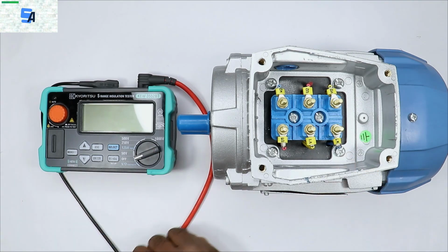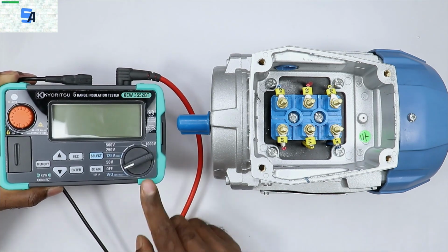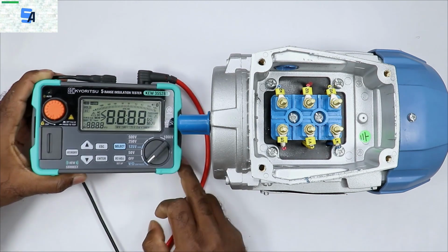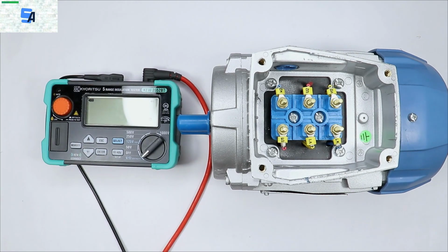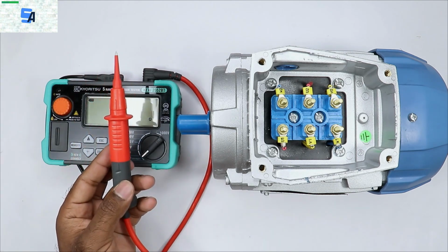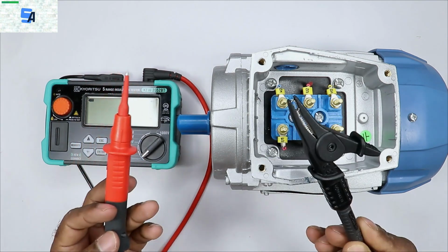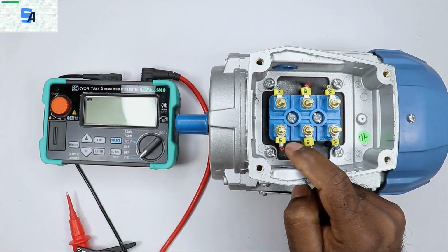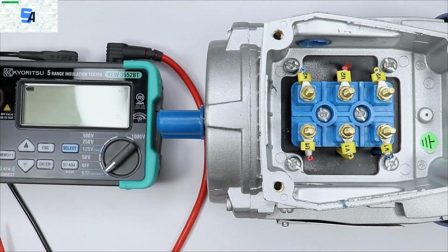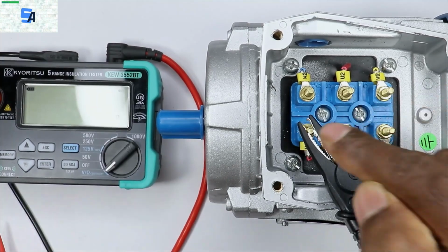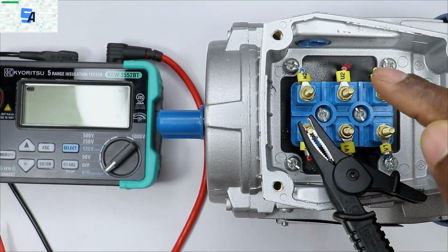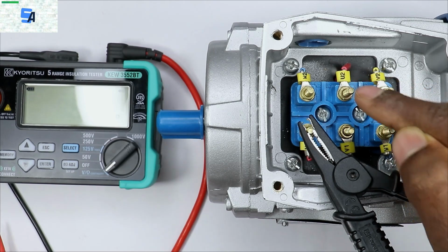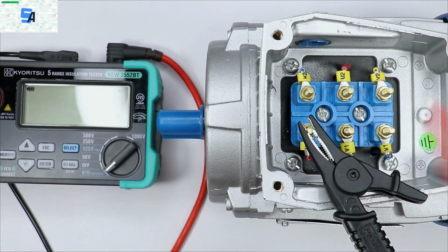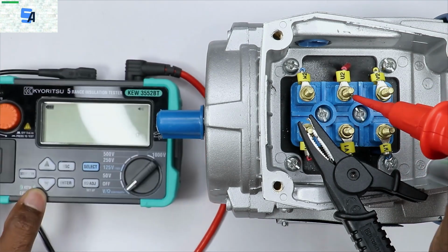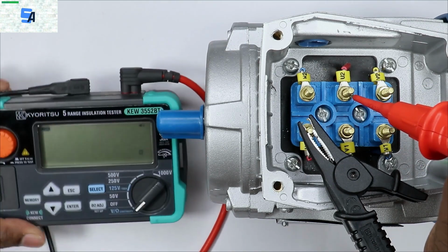What you have to do, simply select the continuity position in the insulation tester. After selecting the continuity position, you will get 2 probes along with the insulation tester. One will be a red probe and the other will be a black probe. Take one probe and connect it with the U1 terminal. The winding connected at the U1 terminal has its other end connected at the U2 terminal. So with the U2 terminal you have to connect the other probe. After connecting this, press the test button in the insulation tester.